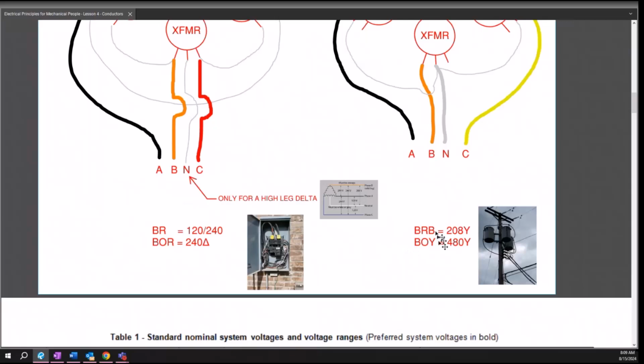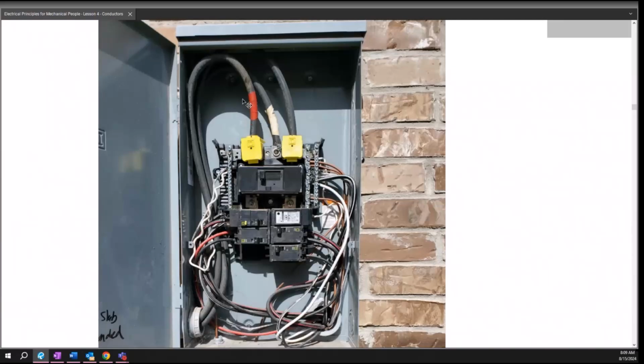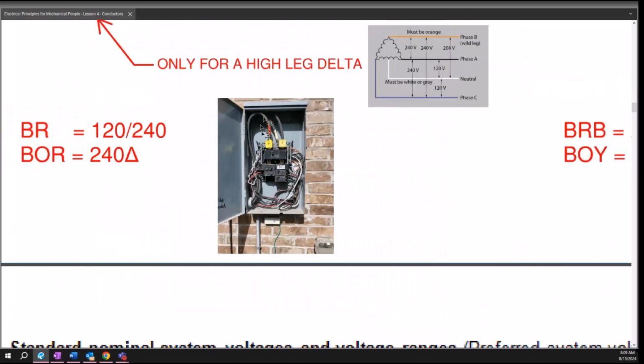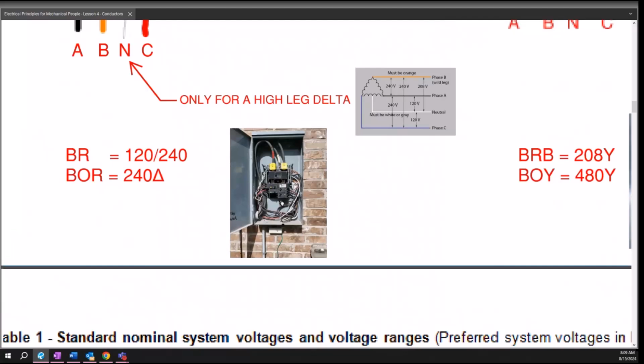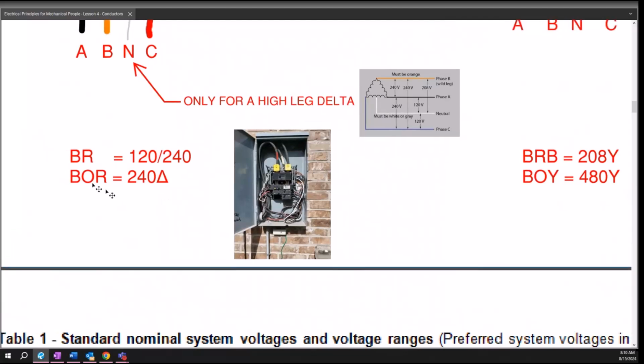Now, the color coding for the voltages is black and red for 120. That's standard. That's in every single household. This is what that looks like. You got red, neutral, black. Okay, so phase, and neutral, obviously. And it doesn't matter which one, red's on the left or red's on the right. That doesn't matter. The 240 delta's going to have the orange in the middle, which I don't have a picture of here.